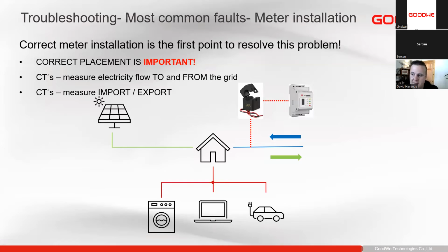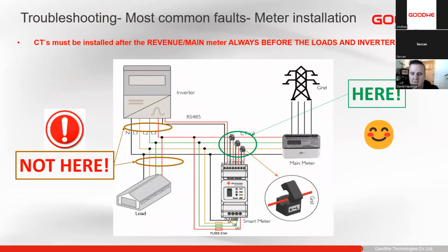Then we also need to make sure that the meter is placed in the correct location. So as we see, it shouldn't be below the inverter. It shouldn't be between the inverter and the loads. It should be between the utility meter and the entire premises. So always as close to the utility meter as possible, before the inverter and the loads. This is so that it can detect any export from the inverter as well as all the consumption of the loads. When we put the CTs here or here, we get very, very strange readings, and it's very hard to diagnose, especially if you install it here between the inverter and the loads, because it will show import, export, import, export, and it doesn't make sense. So it's very hard for us to troubleshoot that. So always make sure to use the provided CTs. Try not to extend the cables at all, and then everything should be correct.